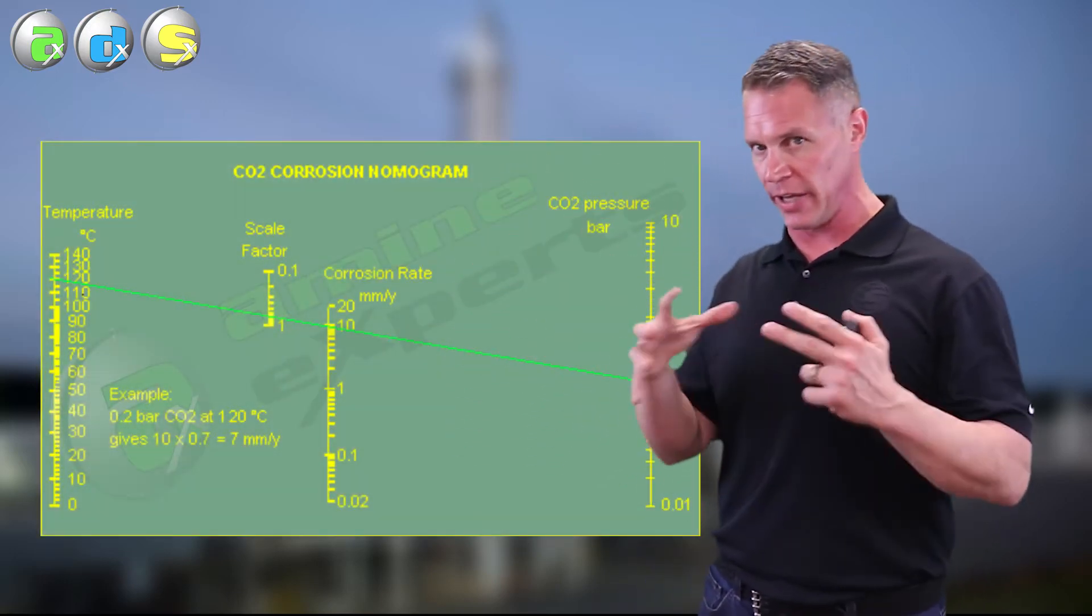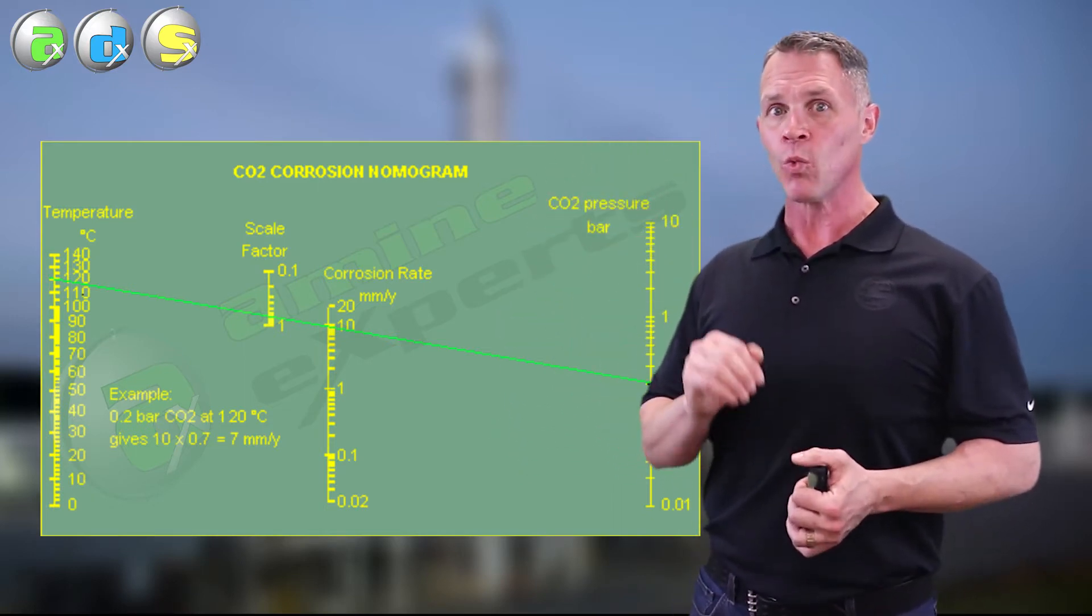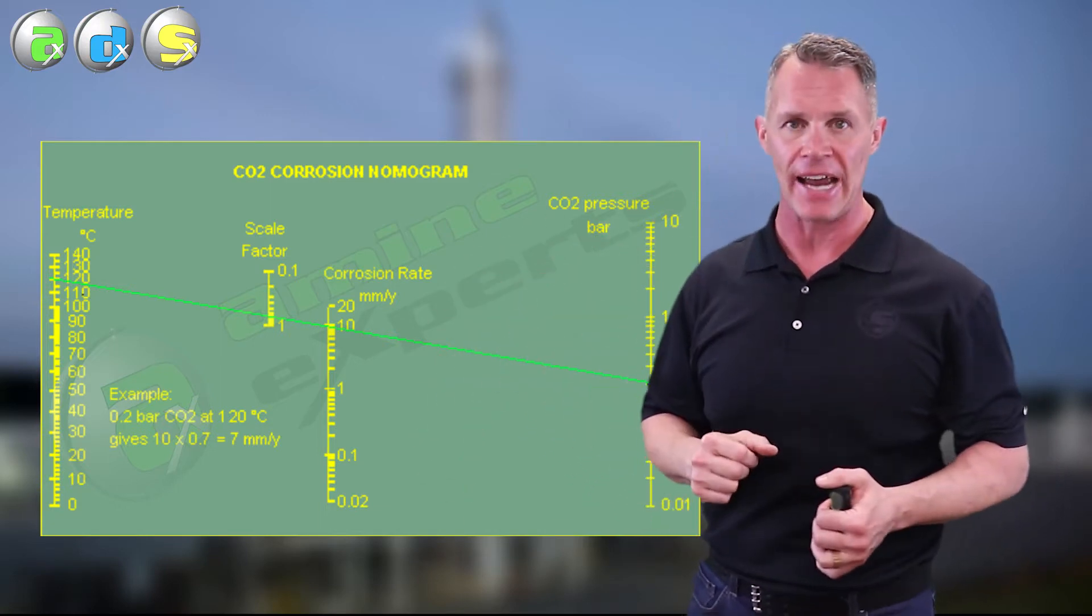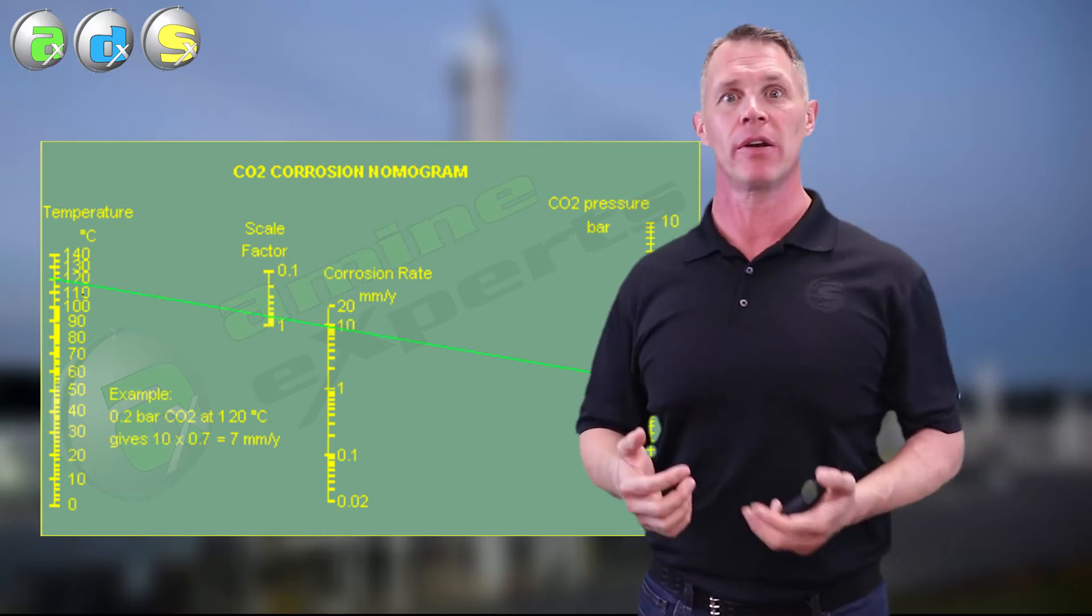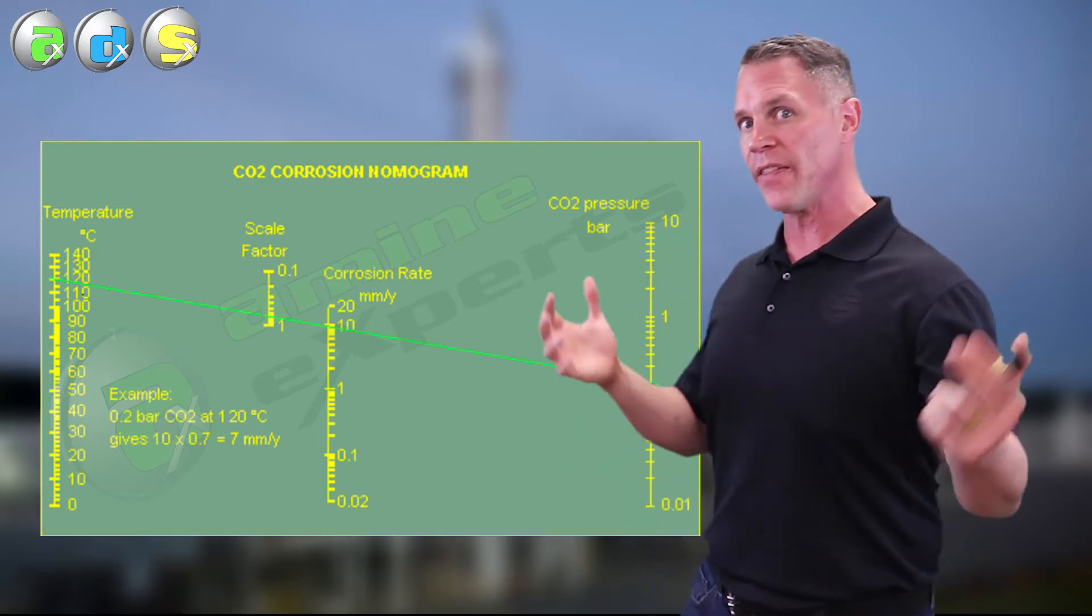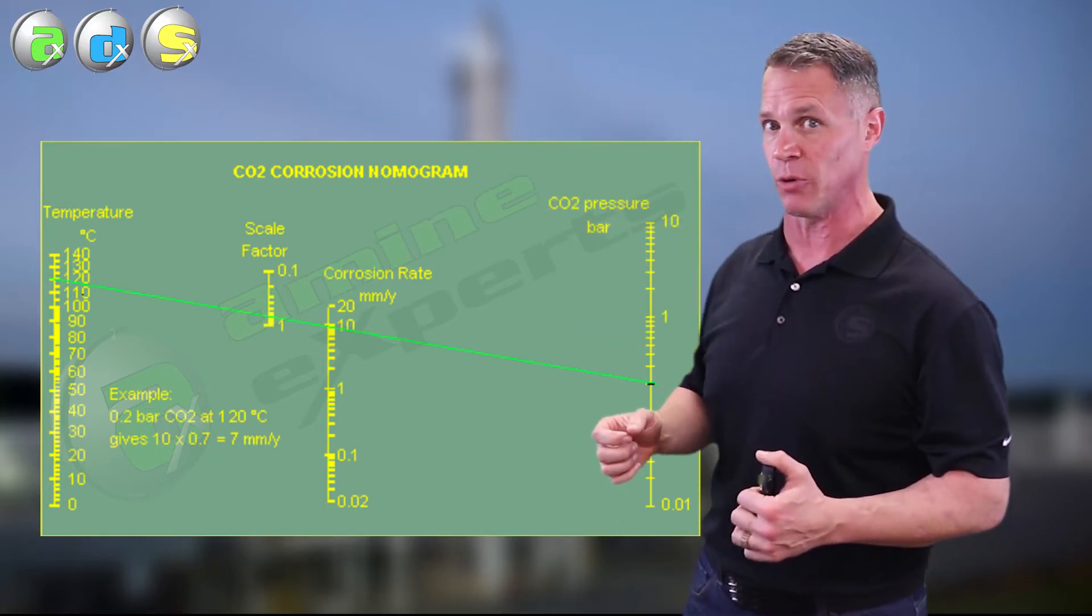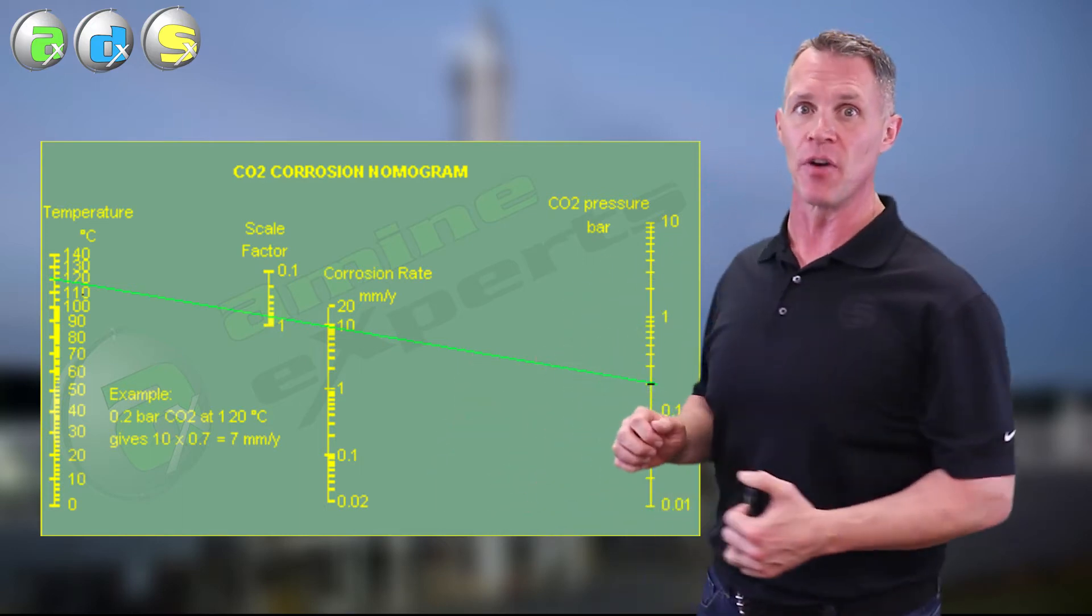Remember back to part one of this video series, we showed a nomograph that illustrated the relationship between CO2 and temperature. Quite simply, we don't want CO2 to be in areas of high temperature in our amine plant. Now of course the regenerator and reboiler are high temperature. So the idea is, when the amine enters the regenerator, we want the CO2 gone as soon as possible. And we definitely don't want CO2 entering the reboiler.